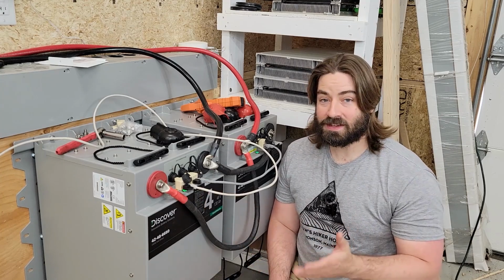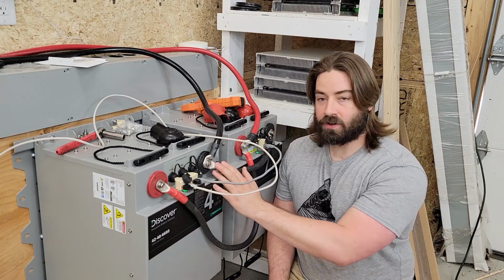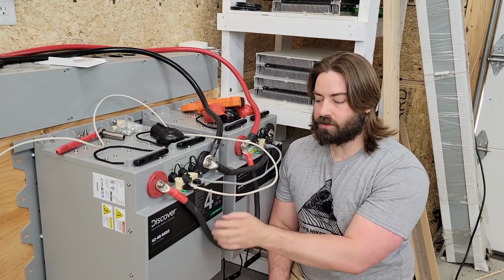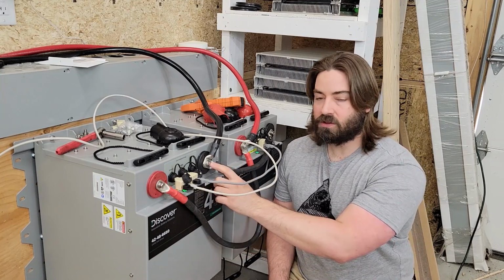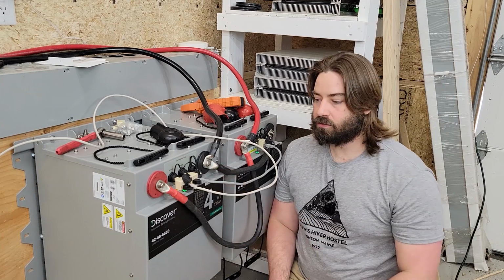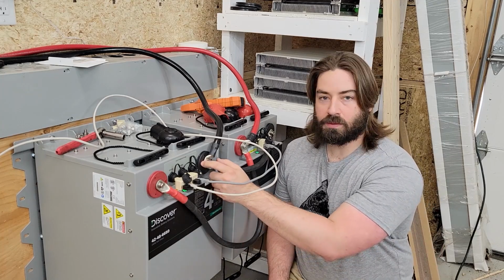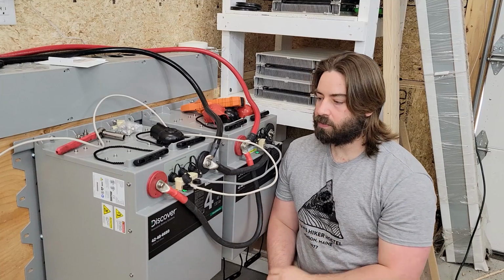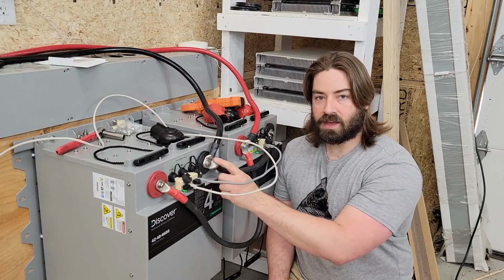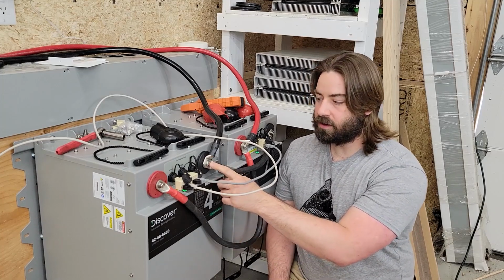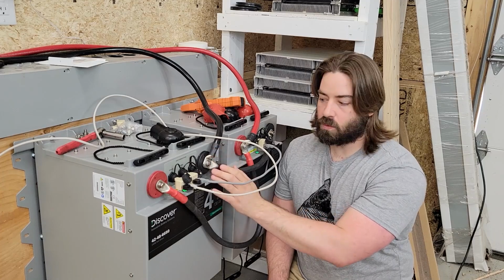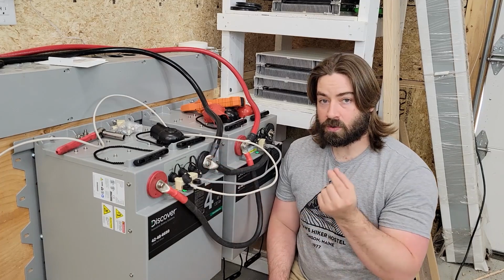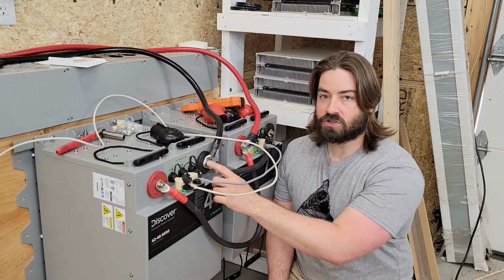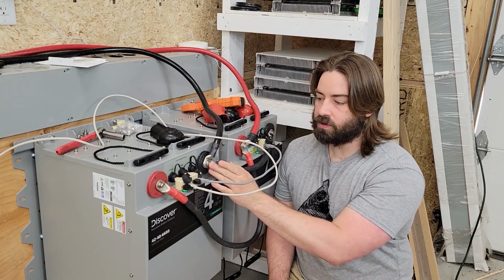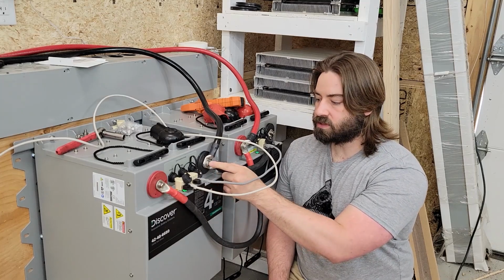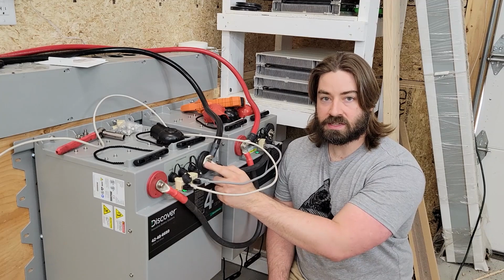I'm not a fan of daisy chaining batteries, but if you're going to do it, remember that all the wires need to be equal length and you need longer bolts. I think these are probably brass terminals built into the battery, so when you're driving a stainless steel bolt into there and put any stress on the wires, if you don't have enough threads engaged, you're going to strip it out. I'd really like to see longer bolts if you're going to daisy chain these and stack your ring terminals.